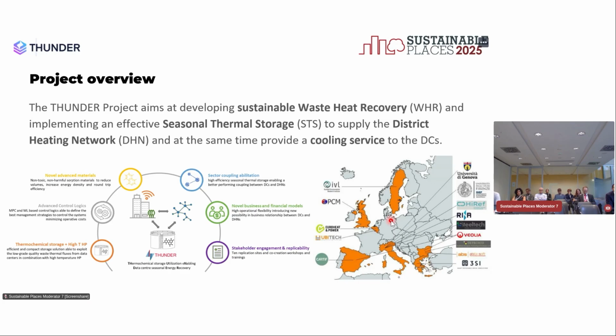Another main objective was cooling the servers in the data center. So as you can see here, the main focus was to develop the thermochemical storage coupled with a high temperature heat pump, in order to increase the temperature and match the charging and discharging temperatures of the thermochemical storage with the temperature from the data center on one side and the district heating network on the other.